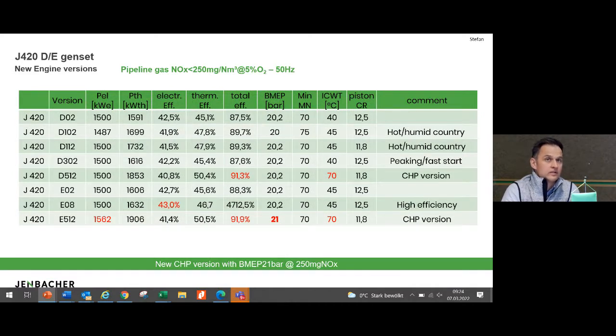Coming to the 250 NOx, as well, we have here hot country versions, the peaking and fast start, as said previously with the D302. This is the one with the permanent pre-lubrication. Then we have as well the D512 as CHP version, a high efficiency version of 250 NOx with the E08 with 43% electrical efficiency. And what is new here with the new concept and the new engine, with this new implementation of the new 3K mixture, we are now able with the E512 as well to allow 21 bar. This means the 1560 kW at 21 bar with a total efficiency up to 91.9% and the higher intercooler water temperature with 70 degrees.